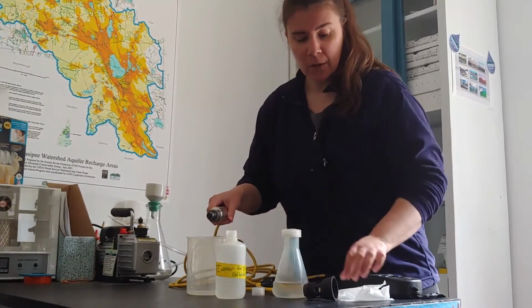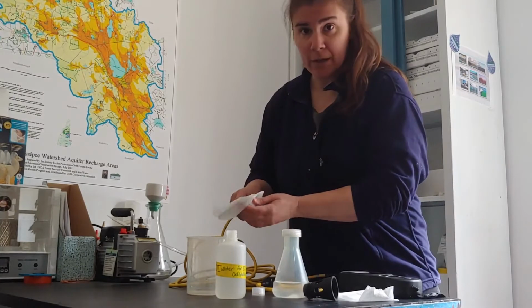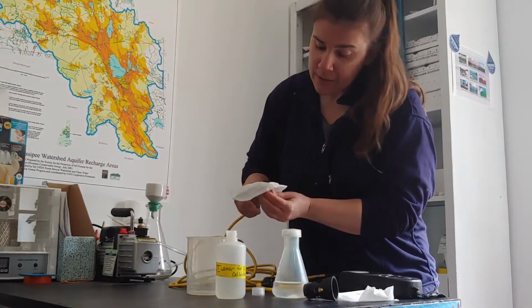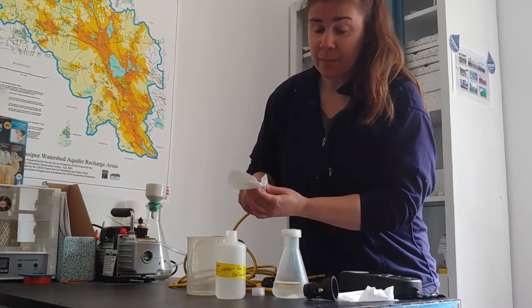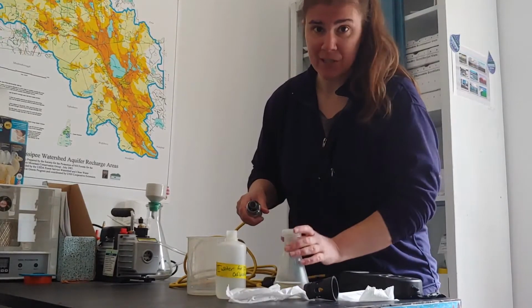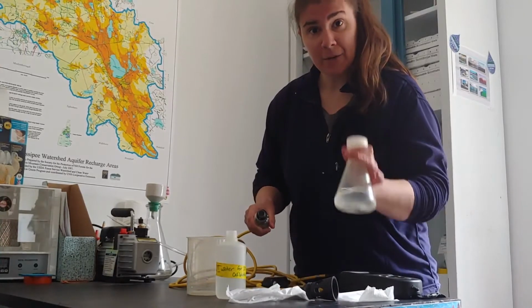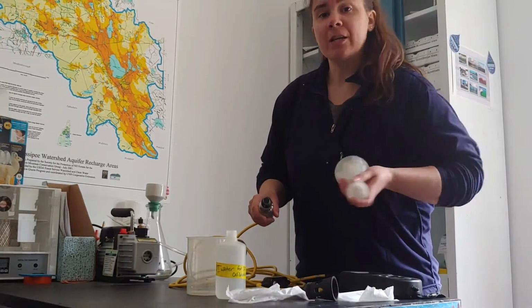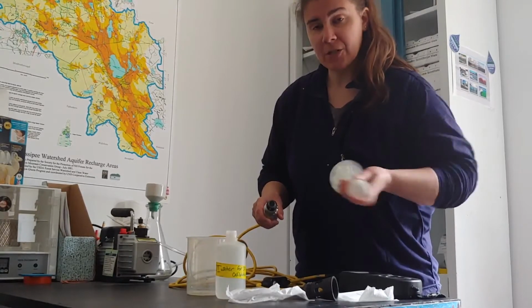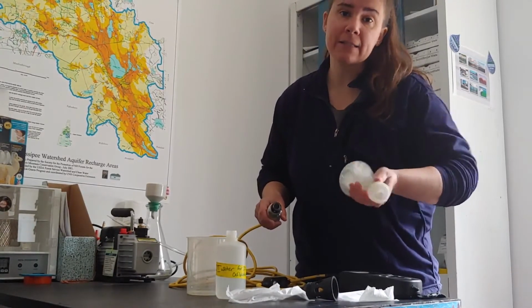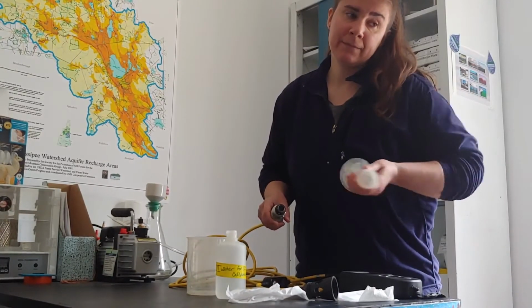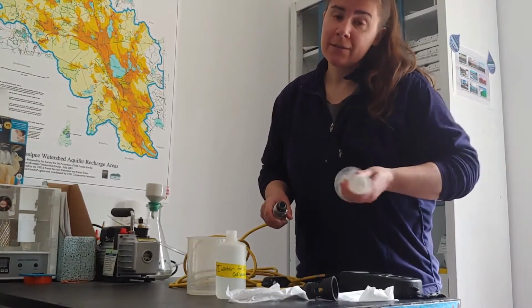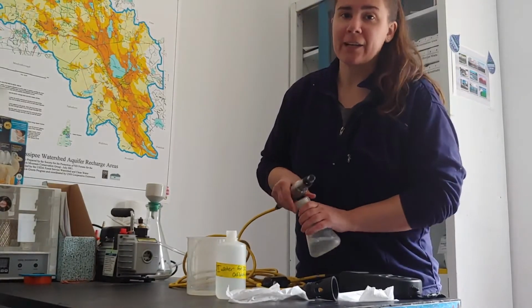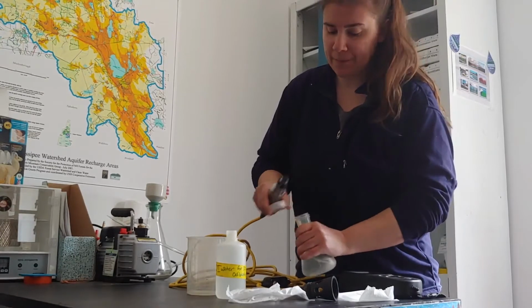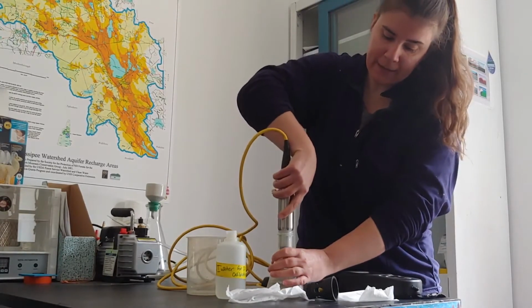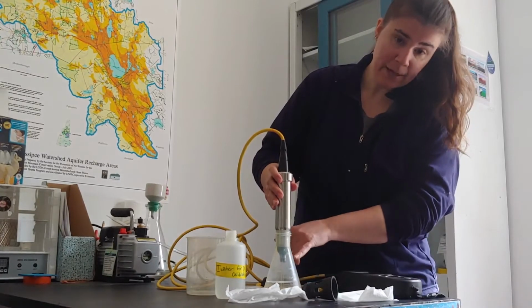Once we've rinsed, we're going to gently dry with our Kim Wipe cloths until there's no water left on the probe. This is very important because if there's water left on the end of the probe, calibration is not going to work. Next, I'm going to take my Erlenmeyer flask and aerate as much as possible by shaking it vigorously for about 30 seconds. So you're not sitting there watching me do this for 30 seconds, we're going to cut it a little bit short. Then we'll open the cap. You'll place your probe inside so that it's not touching the water, but instead it's hovering above the water.